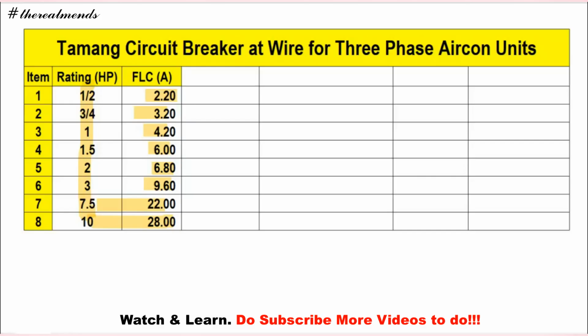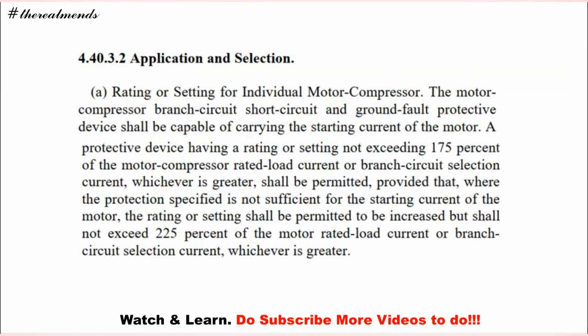So record tayo ulit doon sa PEC, which is coming from the table 4.40.3.2, applications and selection. So at A, rating or setting for individual motor compressor. So the motor compressor branch circuit, short circuit and ground fault protective device shall be capable of carrying the starting current of the motor.